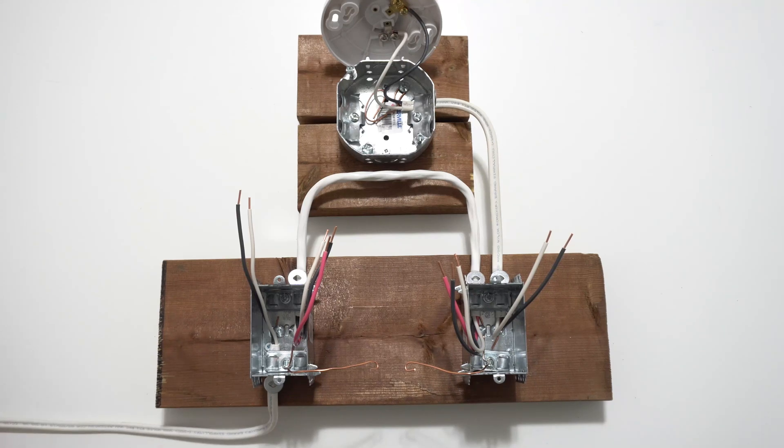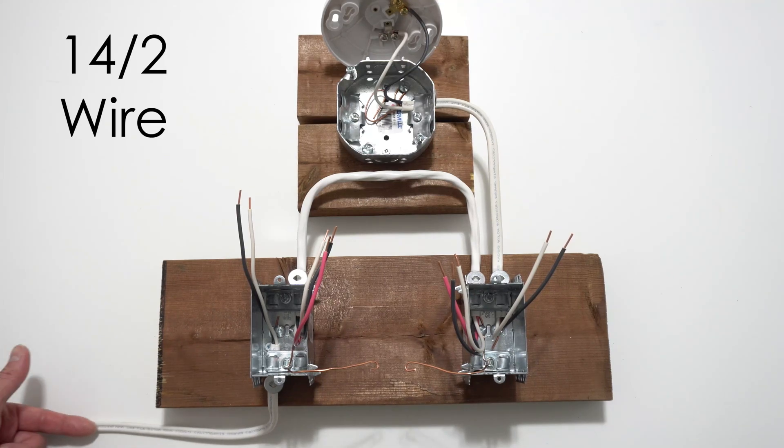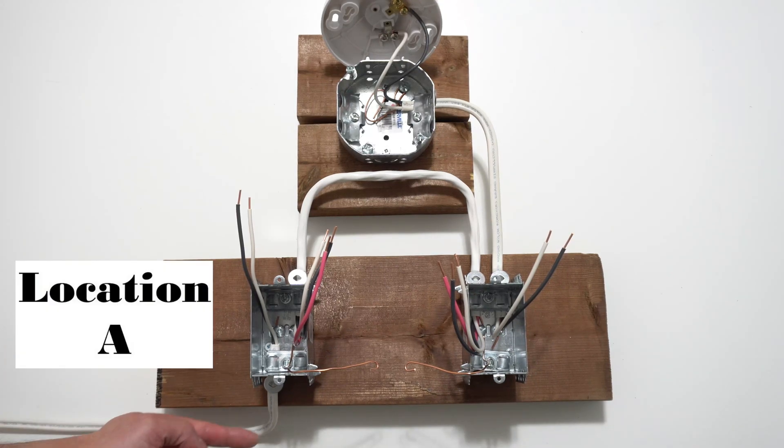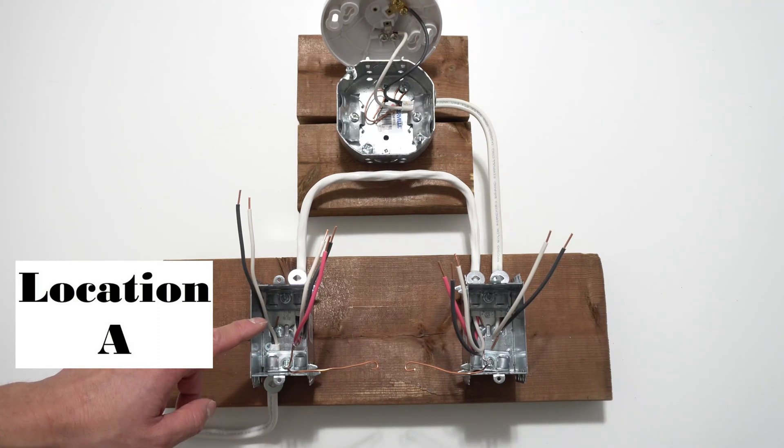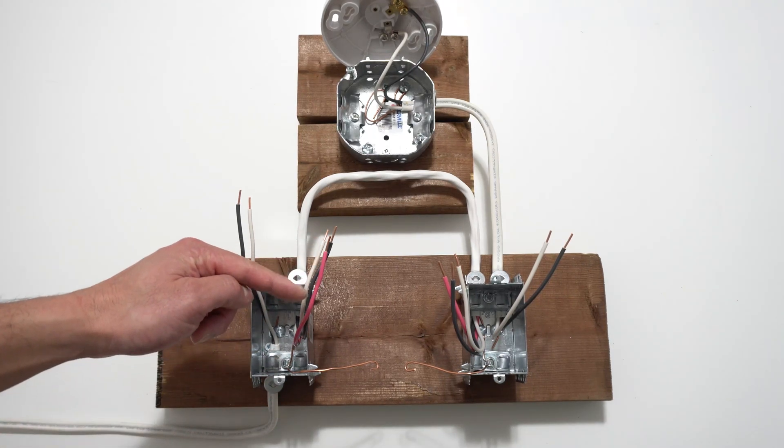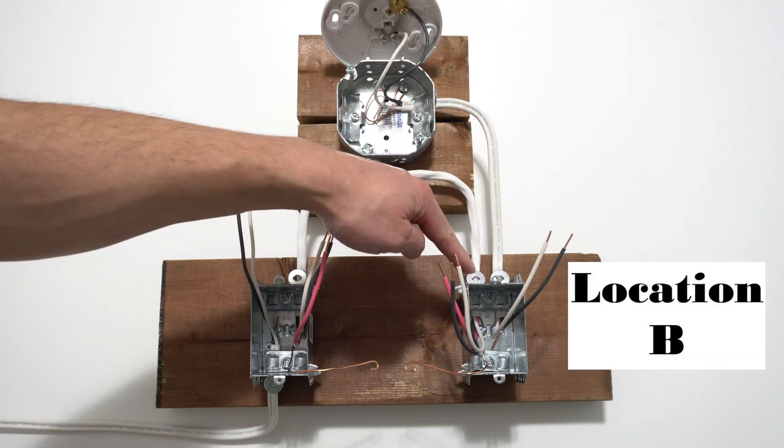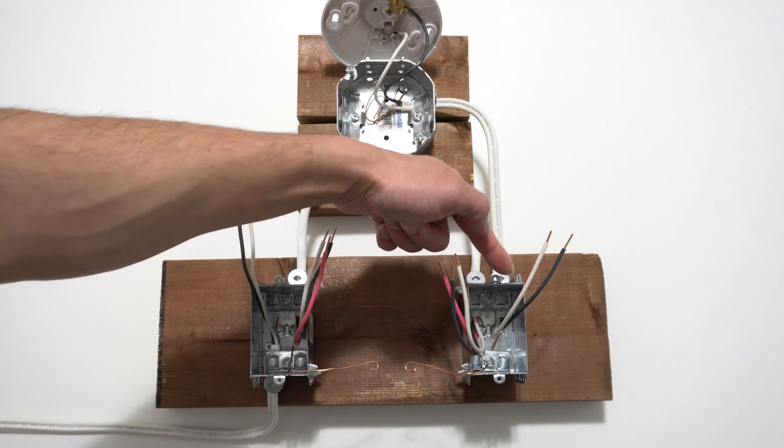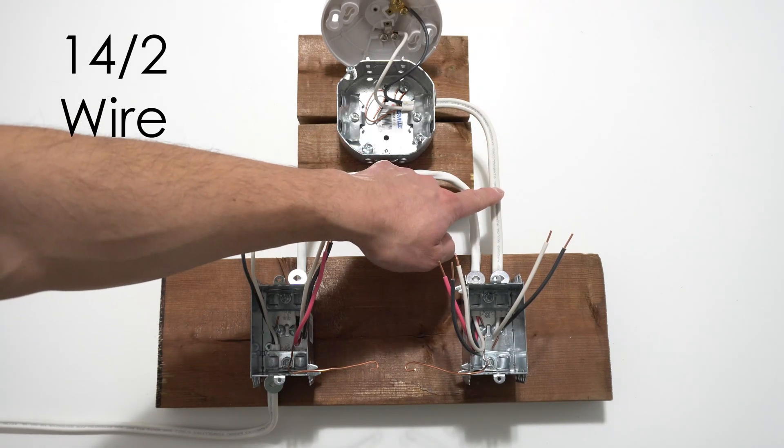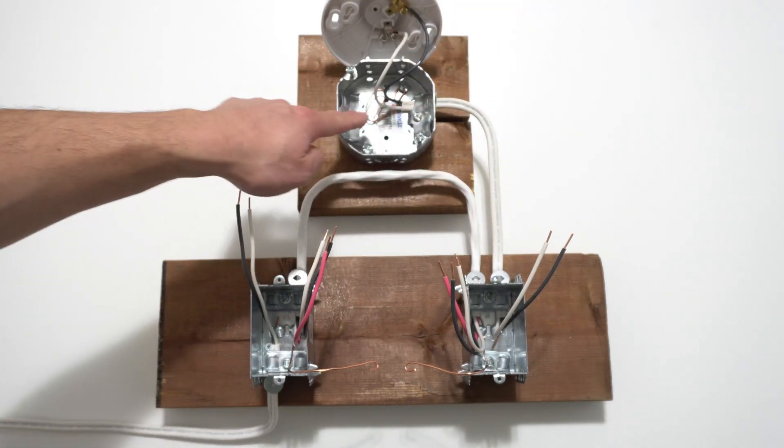Coming in, here we have a 14-2 wire which will carry the power source going into location A box. And coming out of location A box, here we have a 14-3 wire going into location B box. And coming out of location B box, here we have a 14-2 wire going into the light box.